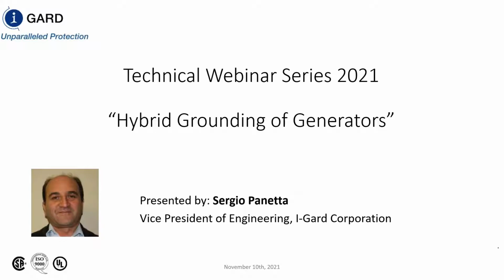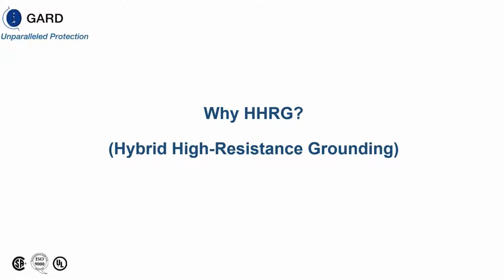So our topic today is going to be hybrid grounding of generators. But hybrid grounding is really hybrid high resistance grounding. So why is it called hybrid high resistance grounding? It's not really a high resistance grounding system. A hybrid high resistance grounding system resembles a low resistance grounding system for the most part, but protects medium voltage bus connected generators when there's an internal fault in the generator. So it switches over to a high resistance grounding system, allowing the generators to coast down and minimizing the damage. And I'll go through what the damage is.